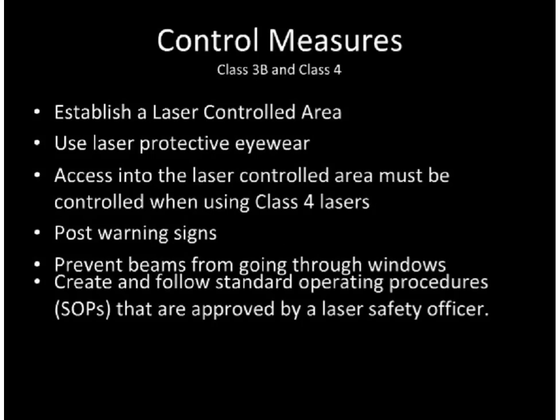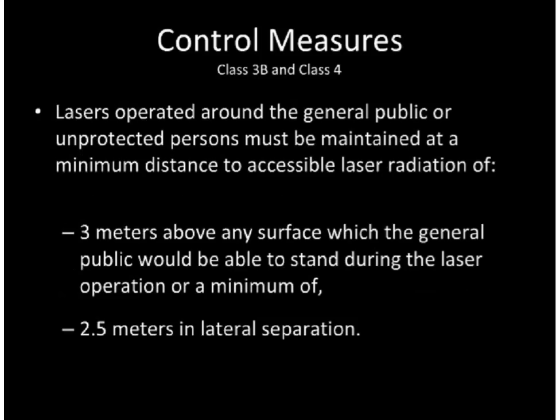Create and follow standard operating procedures that are approved by a laser safety officer. Lasers operated around the general public or unprotected persons must be maintained at a minimum distance to accessible laser radiation of 3 meters above any surface which the general public would be able to stand during laser operation, or a minimum of 2.5 meters in lateral separation.